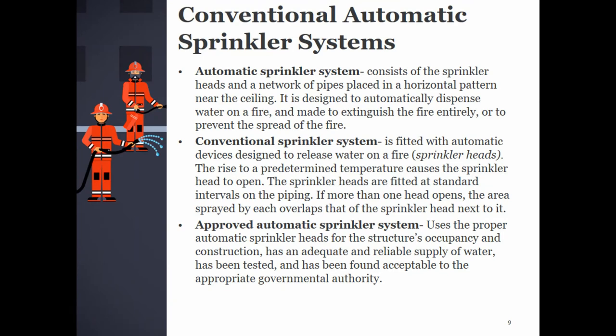Conventional automatic sprinkler systems consist of sprinkler heads and a network of pipes placed in a horizontal pattern near the ceiling. They are designed to automatically dispense water on a fire to extinguish it entirely or prevent its spread. The rise to a predetermined temperature causes the sprinkler head to open. Sprinkler heads are fitted at standard intervals on the piping; if more than one head opens, the area sprayed by each overlaps that of the adjacent sprinkler head. An approved automatic sprinkler system uses the proper heads for the structure's occupancy and construction, has an adequate and reliable water supply, has been tested, and is acceptable to the appropriate governmental authority.